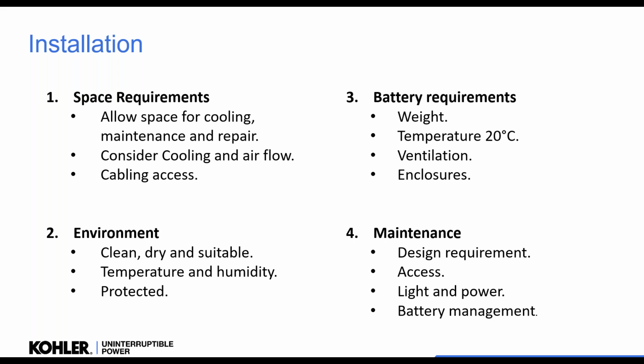A UPS designed to 62040 is designed to be in a clean, dry, dust-free environment, okay, with a controlled temperature and humidity. The environment does have to be fire protected for life safety, but we get a lot of people saying, well, we used to put the generators in this horrible dirty plant room, so let's put the UPS there. It's not designed for it, and they will fail, okay. The batteries are heavy.